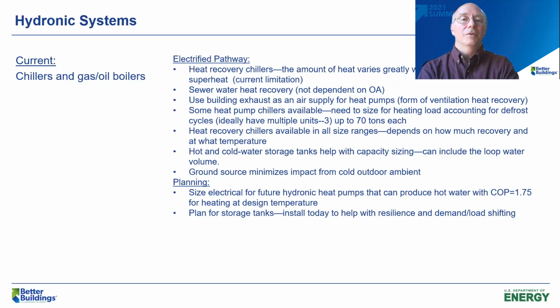There are some chillers specifically called heat pumps. They tend to have a better balance between the amount of heat they can put out and the amount of cooling. In all these systems you have to think about defrost cycles — say you need a little more than two heat pumps, install a third so they can rotate through and not all defrost at the same time. These tend to be available up to about 70 tons each. I'm sure somebody may have a larger one — if you know of one, send it to me so we can update this information.